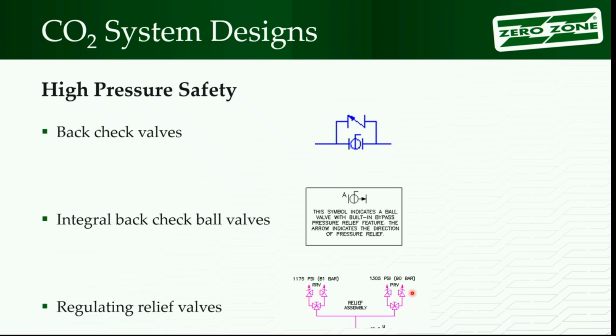Then you say, well, I don't want to have it all of a sudden blow that relief valve down and lose a third of the pressure in the system. I'm going to put on a physically smaller relief valve that's going to burp and let out a little of the CO2 pressure at a time. It might continue to burp, right? Power's still out, pressure comes up, it burps them out. Power's out, burps them out. So you'll put in a second set. That's what you have here, called a regulating relief. Notice the set pressure is less than the main pressure in the system. So this one's going to release first.